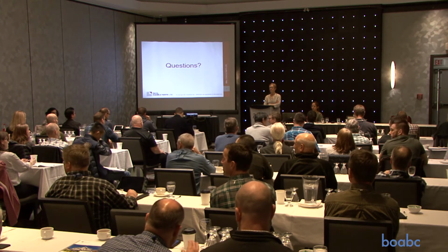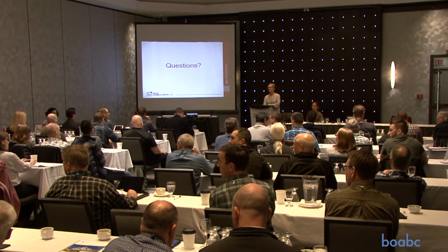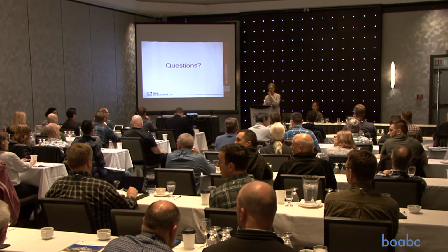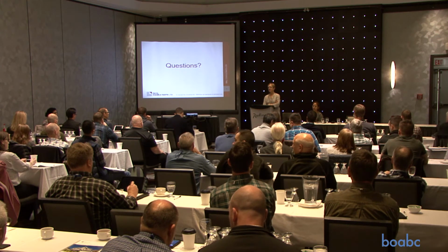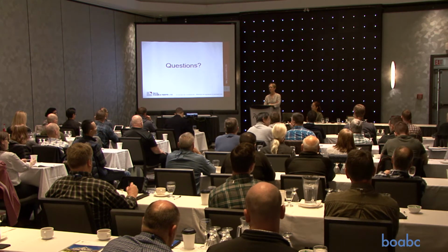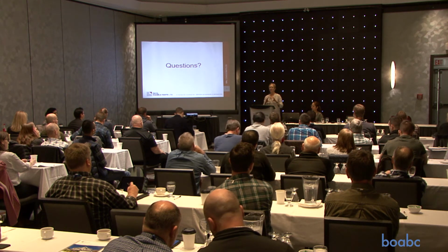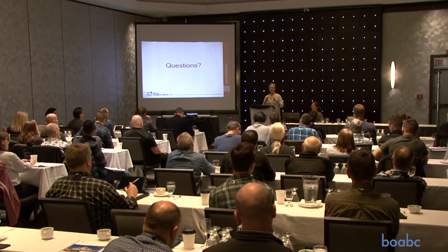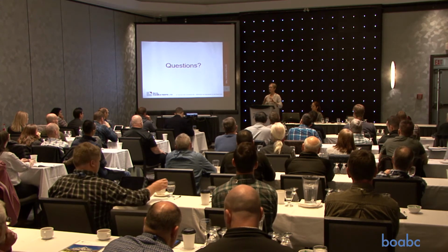There's lots of fire resistant products out there, but they don't have a rating. Yeah, there's lots of things that say they're lots of things, and then when you start looking into it, somebody sent me a rated outlet box, like a plastic outlet box with a fire resistance rating, 2 hours.